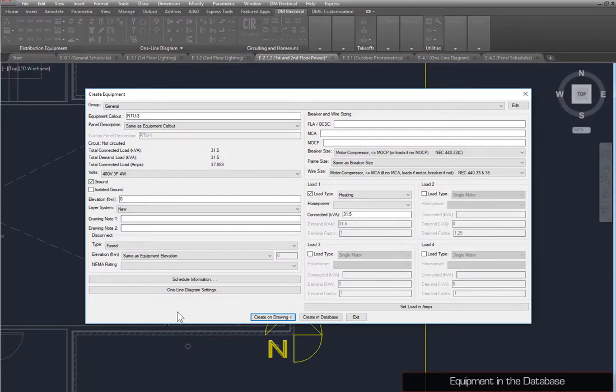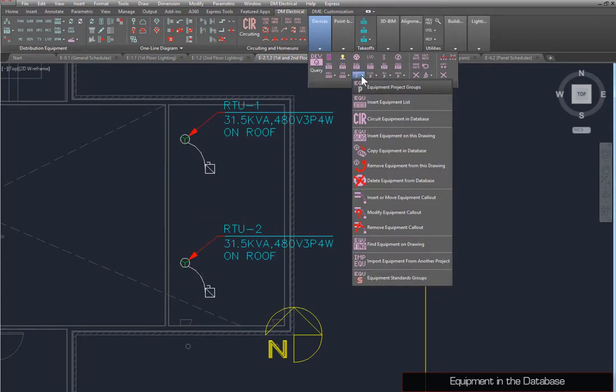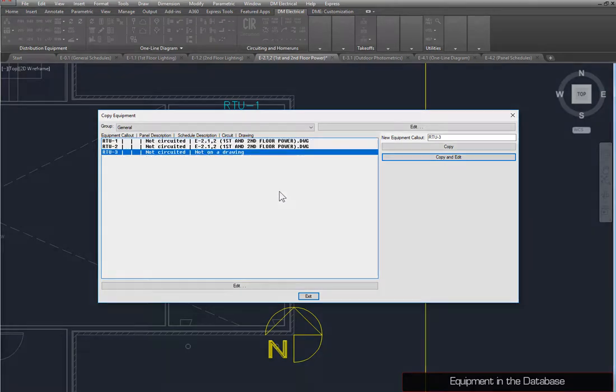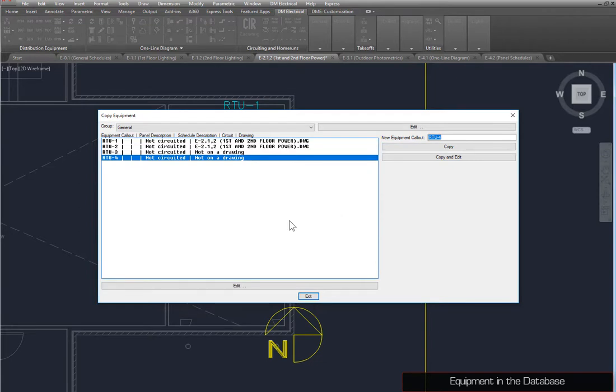To demonstrate how equipment can be created in the database without inserting it on the drawing, we've used the Create Equipment command to create a piece of equipment with these settings. Press the Create in Database button. A dialog box will confirm that the equipment has been created. We'll copy the equipment we just created using the Copy Equipment in Database command. Select RTU3, set the New Equipment Callout to RTU4, and press the Copy button. You can also use the Copy and Edit button to copy an equipment and immediately edit the settings for the copy.